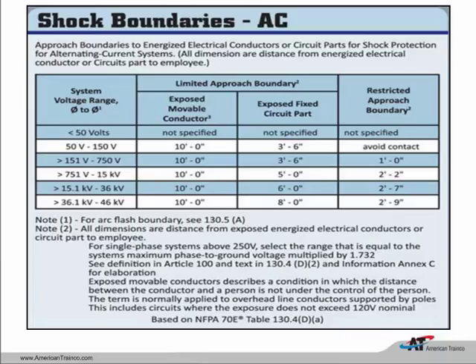And all they're doing on the restricted approach boundary is basically telling us don't touch 120 volts. So we just have to be careful in that area. When we get up into the 208 three-phase and 480 volt three-phase range, we can see now that the restricted approach boundary did come back, and we are going to have to make sure we have shock protection on for that particular area. But they did give us a little bit of leeway with 120 volts. They did also give us an idea that at 208 volts, we want to make sure we know we have that restricted approach boundary there. So they played a little bit with the shock boundaries for AC.